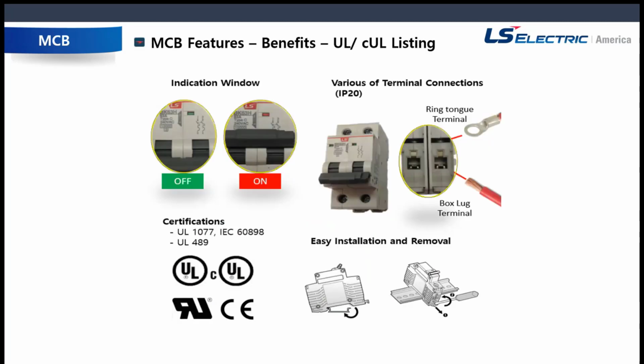So here we go. Here are some of the benefits of the MCB. Our MCBs have an indication window, so you can really tell whether or not it's on or off, which again is crucial in operating. You can have ring tongue or box lug terminal. And as you can see by the DIN rail mounts at the bottom, it's easy to install and remove without much hassle. And our certifications are below. We do both UL and IEC.